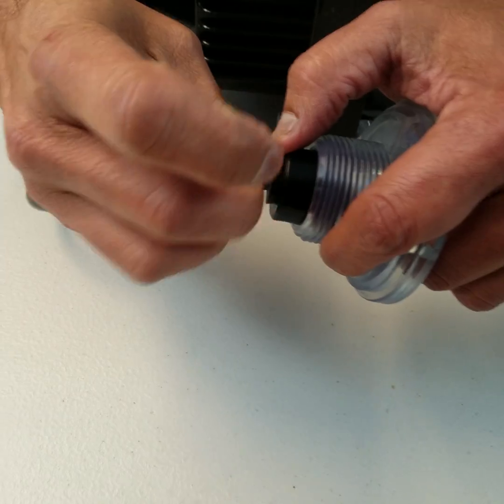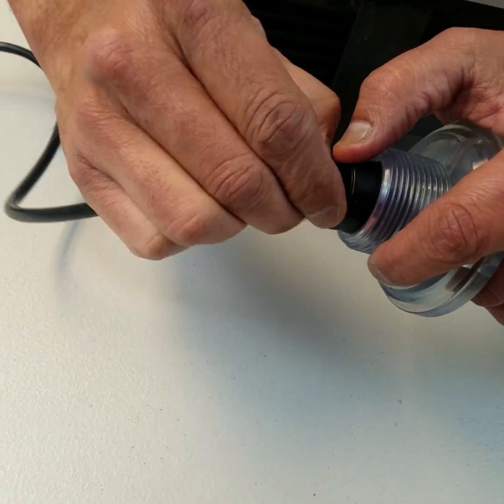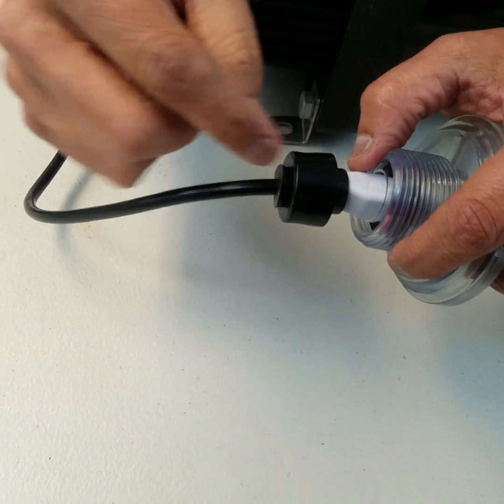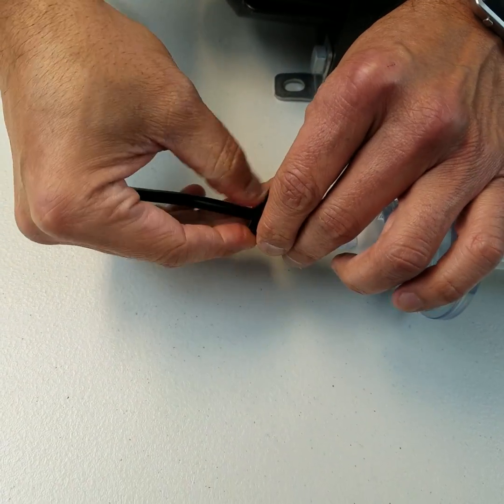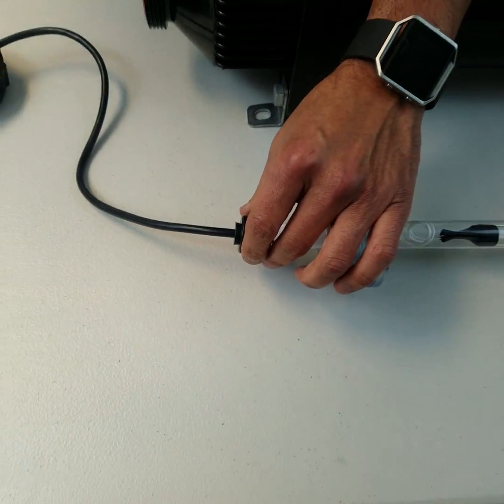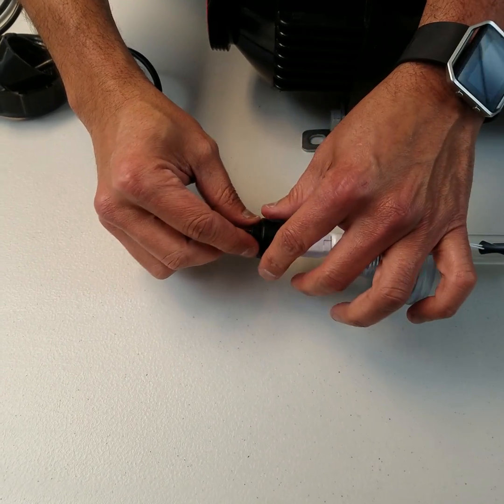Here you see this little rubber part here. Make sure that this is locked in place. Just to give you an idea what it does: this rubber part is the mechanism that seals and compresses the cable with the quartz sleeve so no moisture goes in.